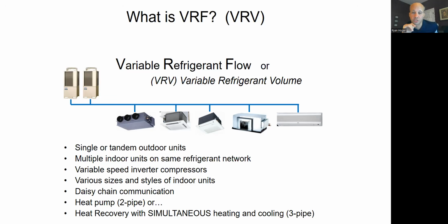Whereas old school, traditional, plain single stage heat pumps typically don't have those switches, because those things are being designed for first cost markets in Georgia, right? So they don't have those extra protection devices unless somebody upgrades to the nice model. So if you have too low or too high of refrigerant, like really too low and really too high, the machine will just shut off and protect itself.